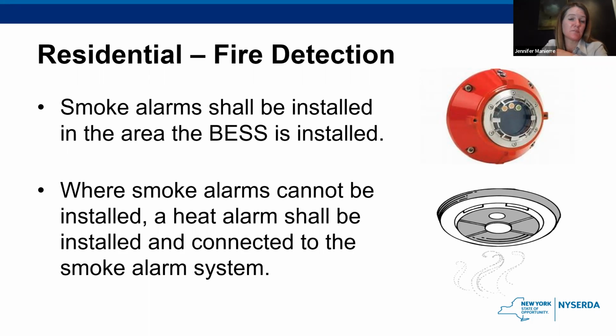Residential systems need smoke alarms to be installed in the area where the energy storage system is installed. If for some reason smoke alarms can't be installed, you can do a heat sensor.